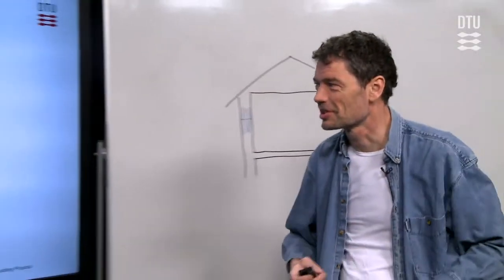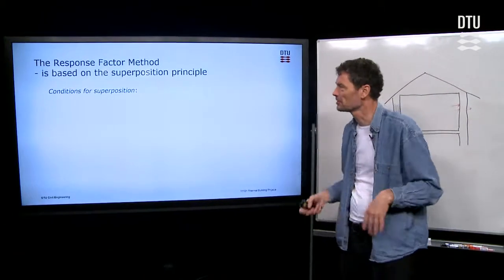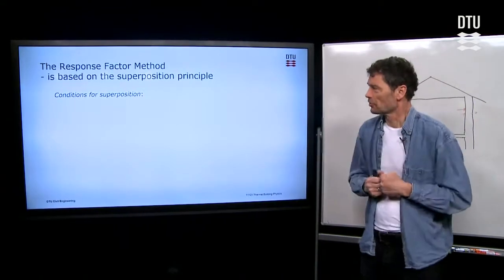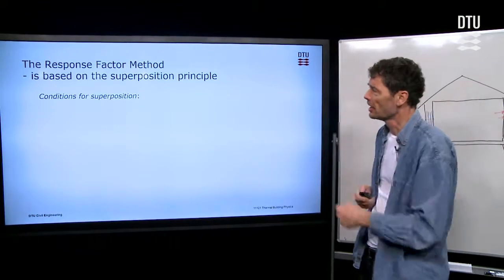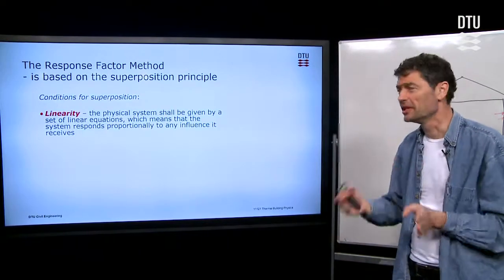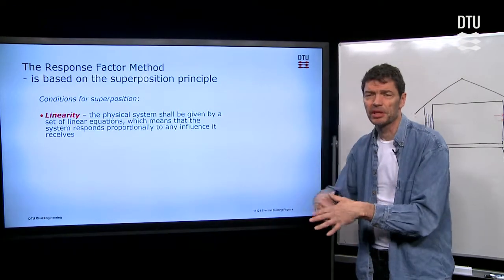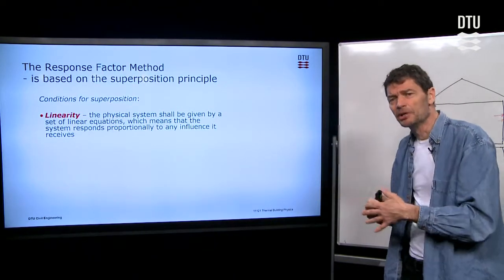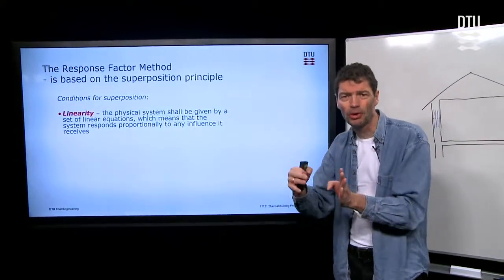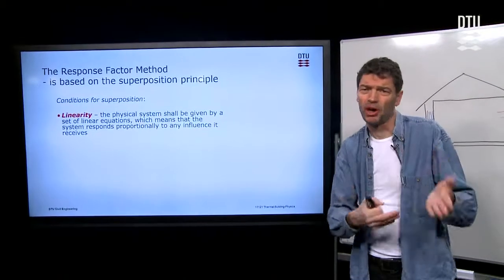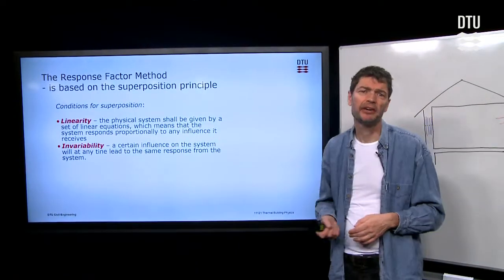So let's go back to the slides to explain a little bit more what it is. For the response factor method, a fundamental principle is superposition. And conditions for that is that we have linearity, which essentially means that if we have several responses, we can add them up. So for instance, if you have twice as large temperature impulse on a wall, then also the heat flows will double. That's in principle what this says with the linearity.